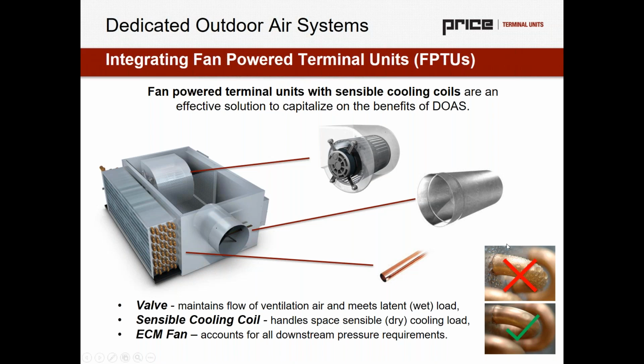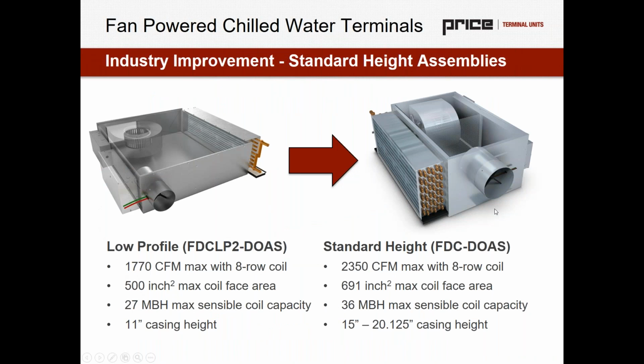So the other reason why this equipment has become more popular in really the last year, let's say, is because there have recently been some significant industry improvements. Those are based in the fact that this equipment has been modified and updated for the wider market with a standard height casing. A standard height casing is centered around 18.5 inches of height, but spanning from 15 to 20 and 1/8 in the case of the Price terminal unit.